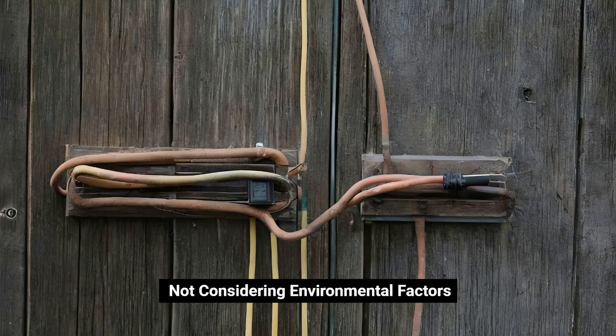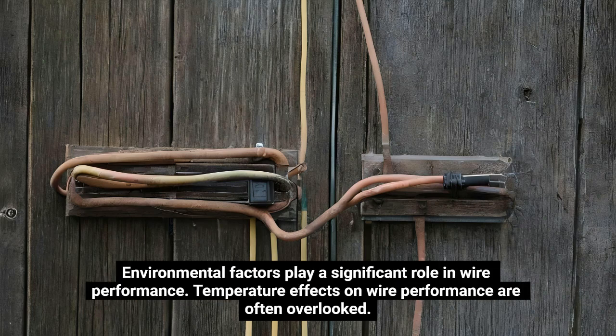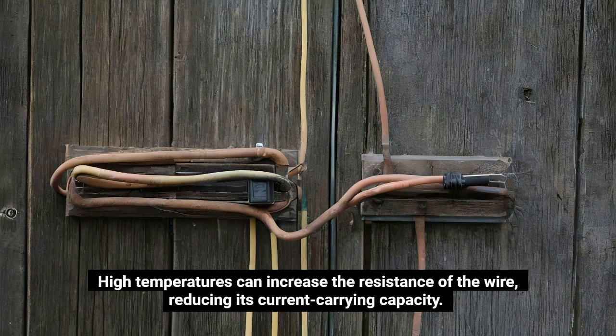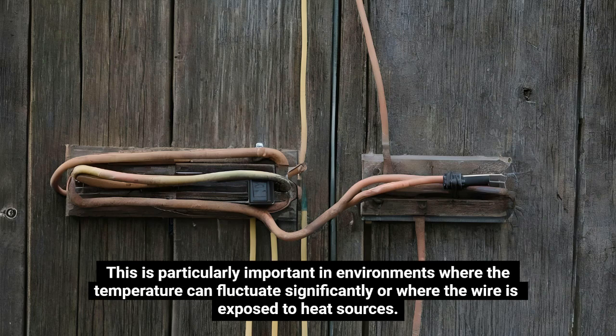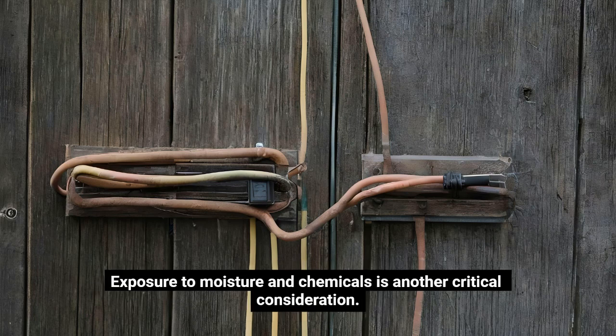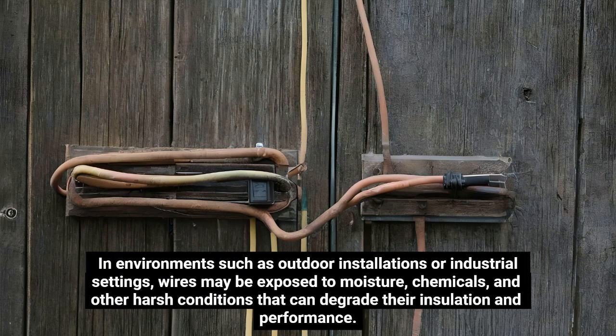Not considering environmental factors. Environmental factors play a significant role in wire performance. Temperature effects on wire performance are often overlooked. High temperatures can increase the resistance of the wire, reducing its current carrying capacity. This is particularly important in environments where the temperature can fluctuate significantly or where the wire is exposed to heat sources. Exposure to moisture and chemicals is another critical consideration. In environments such as outdoor installations or industrial settings, wires may be exposed to moisture, chemicals, and other harsh conditions that can degrade their insulation and performance.